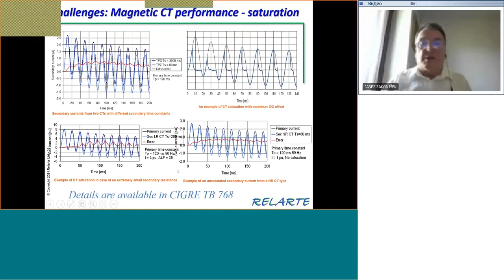If we look a little bit at the Rogowski coil, which is considered a low power or non-conventional instrument or current transformer, then it's necessary to consider also, which I would say not so many people know, that the Rogowski coil signal really gives you the di/dt signal. So the change of current over time, this is what is really measured by the Rogowski coil. And when we look into this, let's say we have primary current here. This is the black picture. The red one is what comes out from the Rogowski coil, the di/dt.